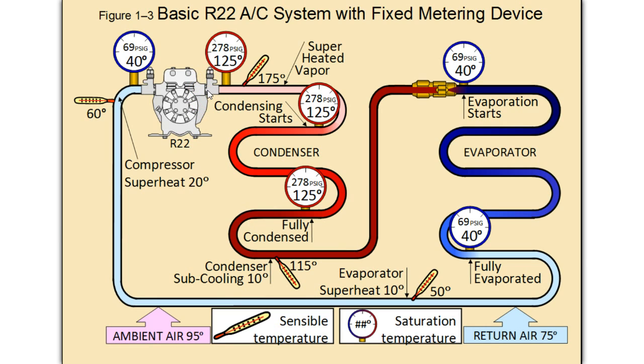We have superheated, high-pressure, high-temperature vapor leaving the compressor at the beginning part of the condensing unit. That high-pressure, high-temperature superheated vapor is desuperheated once it hits the saturation point at 125 degrees, and condensing begins.